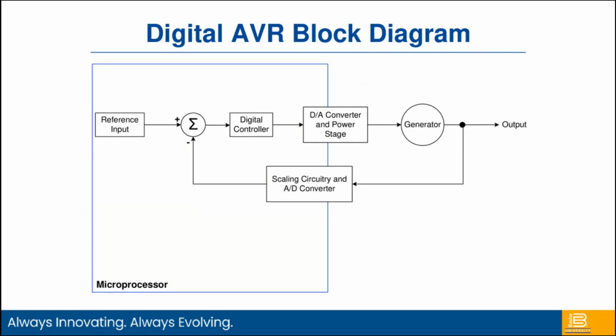And just like the analog regulator, we've got a reference input. That is our set point. It's going to compare the set point to the output of the generator terminals. Then we're going to go through our digital controller, where the voltage regulator is going to work its magic and determine what needs to happen internally. And then we go back and we're going to take that digital signal. This is like that firing circuit part.